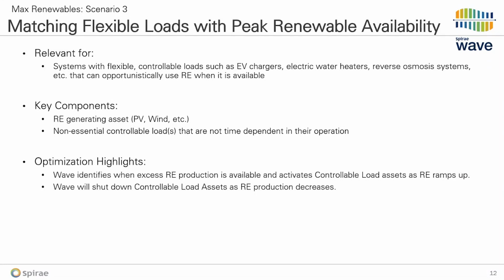So for the next scenario, we're going to take a look at those flexible loads that we have in the system. These might be electric vehicle chargers, they might be electric water heaters, could be reverse osmosis systems. We've seen that in literal island applications. So you can imagine these as non-essential controllable loads that may not be time dependent in their operation. So we can leverage these as part of our control system to take advantage of periods of time where we do have that excess generation available from our renewable assets. And instead of curtailing, we can turn these loads on instead and make best use of that available energy.